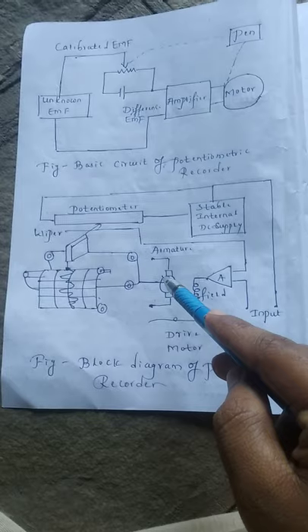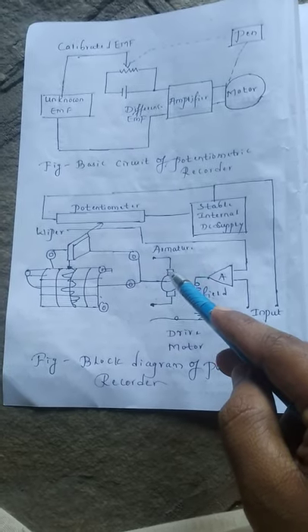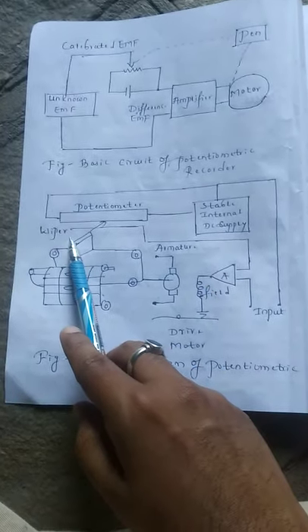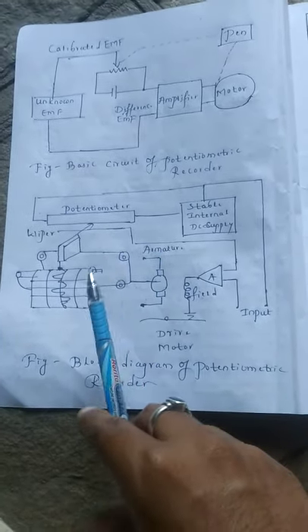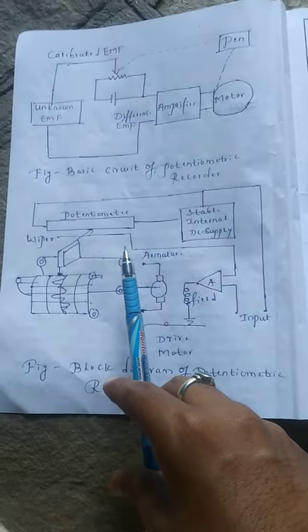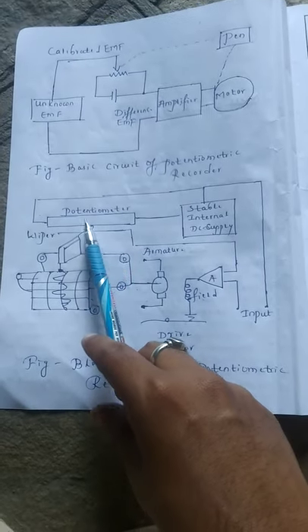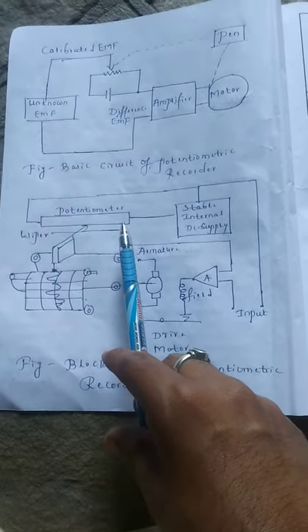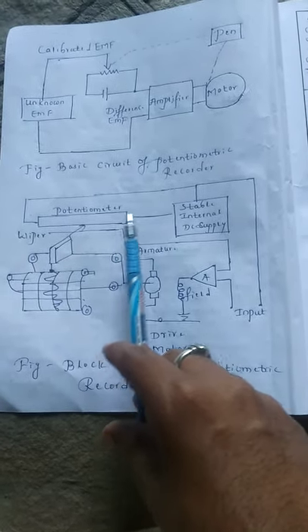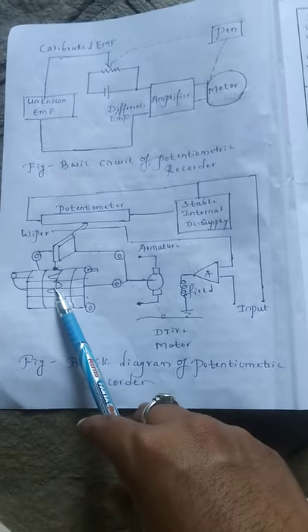This is achieved by mechanically connecting the wiper or variable arm to the armature of the DC motor. The pen is also mechanically connected to the wiper. Hence, when the wiper moves in a particular direction, the pen also moves in synchronism in the same direction, thereby recording the input waveform.